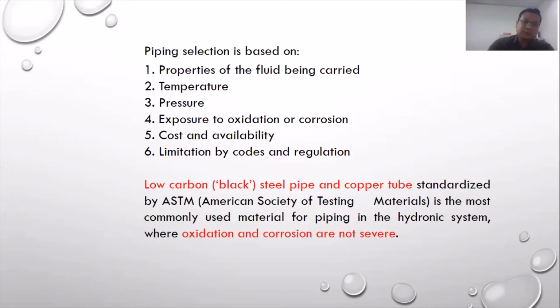Okay, as we know, for the material of piping, low carbon black steel pipe and copper tubes are commonly used in the HVAC system, standardized by ASTM, short form for American Society for Testing and Materials. It is the most commonly used material for piping in the hydronic system, where oxidation and corrosion are not severe.